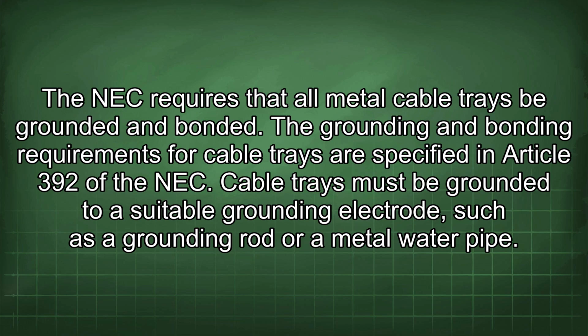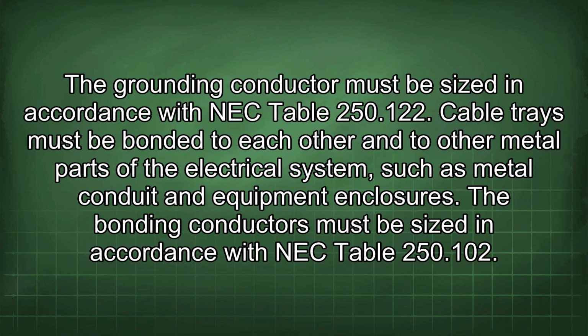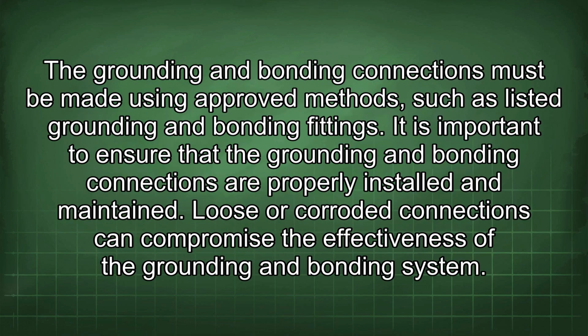Cable trays must be grounded to a suitable grounding electrode, such as a grounding rod or a metal water pipe. The grounding conductor must be sized in accordance with NEC Table 250.122. Cable trays must be bonded to each other and to other metal parts of the electrical system, such as metal conduit and equipment enclosures. The bonding conductors must be sized in accordance with NEC Table 250.102. The grounding and bonding connections must be made using approved methods, such as listed grounding and bonding fittings.